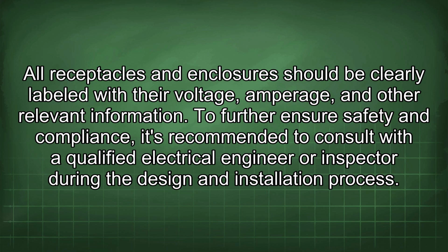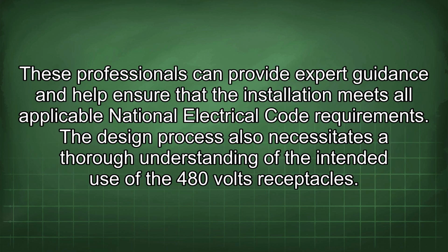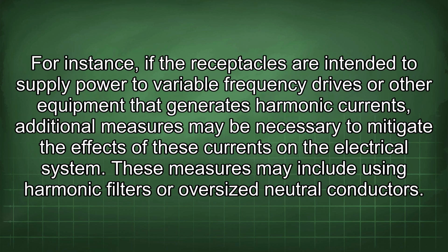To further ensure safety and compliance, it's recommended to consult with a qualified electrical engineer or inspector during the design and installation process. These professionals can provide expert guidance and help ensure that the installation meets all applicable National Electrical Code requirements. The design process also necessitates a thorough understanding of the intended use of the 480-volt receptacles. For instance, if the receptacles are intended to supply power to variable frequency drives or other equipment that generates harmonic currents, additional measures may be necessary to mitigate the effects of these currents on the electrical system. These measures may include using harmonic filters or oversized neutral conductors.